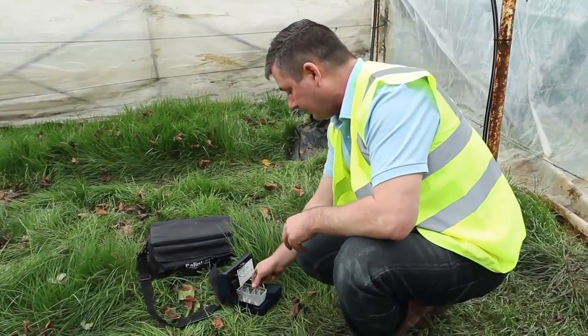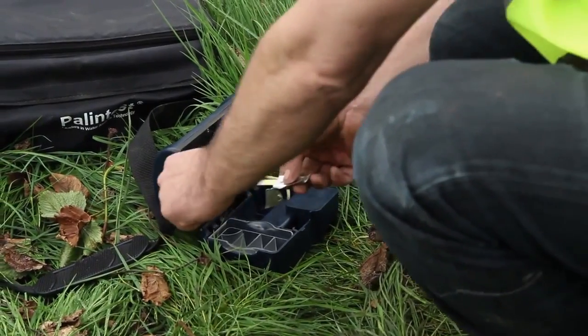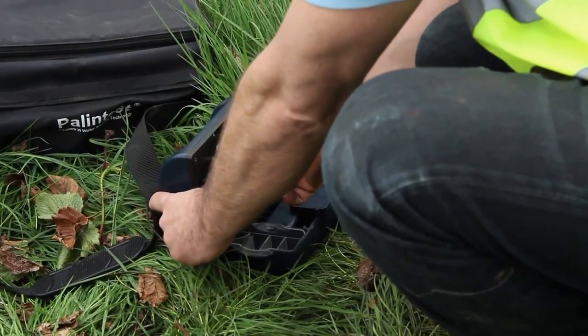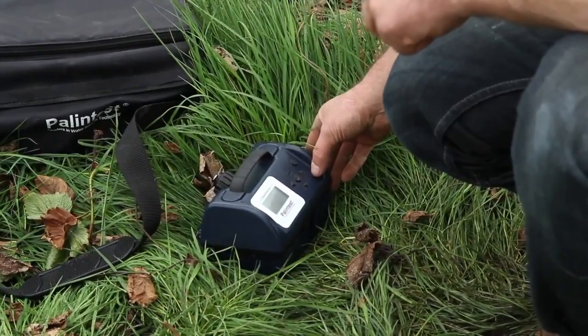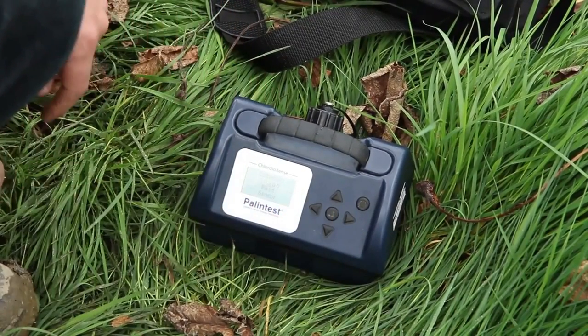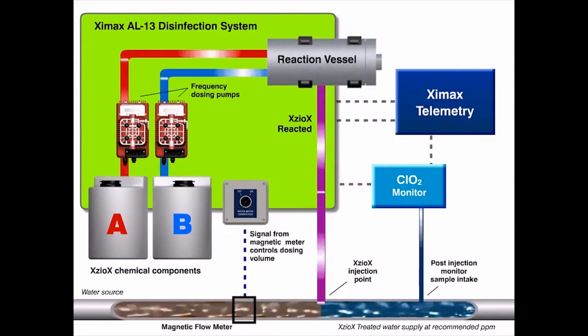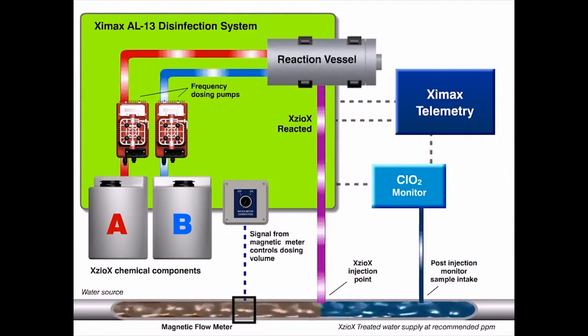The chemical dosing rates required on any given site are unique, as they are dependent upon the water source and quality. Following installation of the AL-13 dosing system, the engineer will take residual chlorine dioxide readings at key sections of the irrigation system, and then calibrate the system to ensure that the precise XzioX dose is delivered to the drip lines for optimal pathogen elimination.